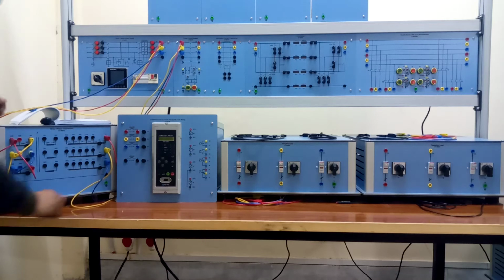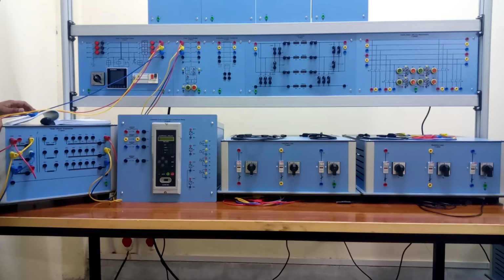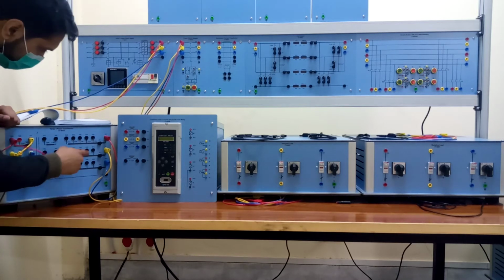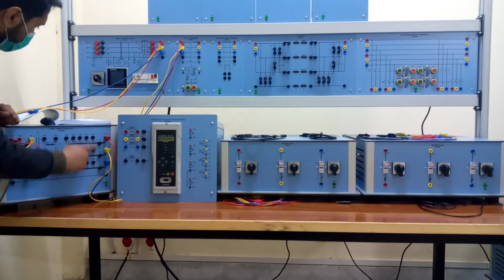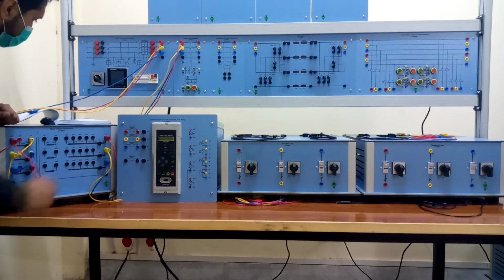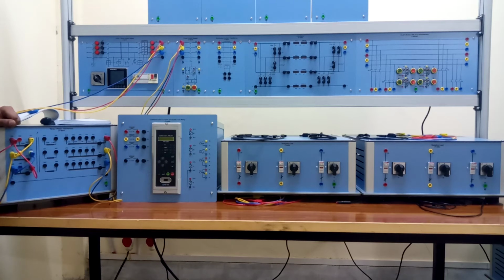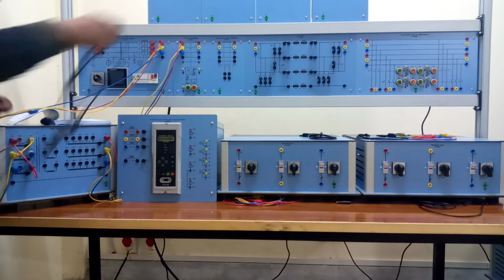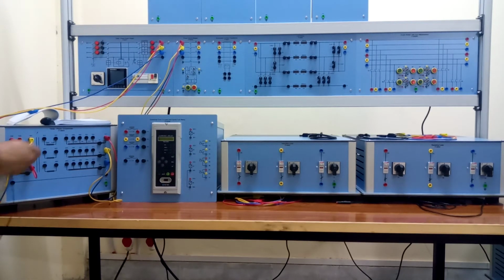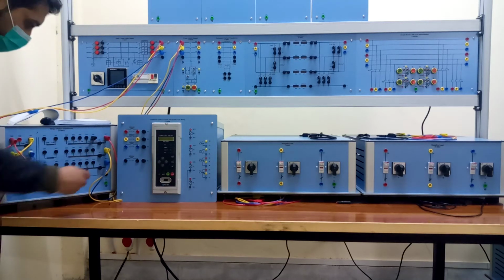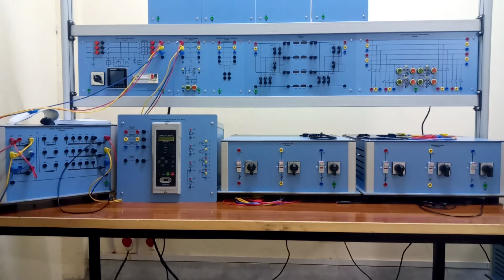Next, we have to combine these neutrals, and this will be connected to minus 15%. So we will combine all these connections together, and this will be your star point. I'm going to connect them using the neutral wires, the black wires. This is the minus 15% tapping.